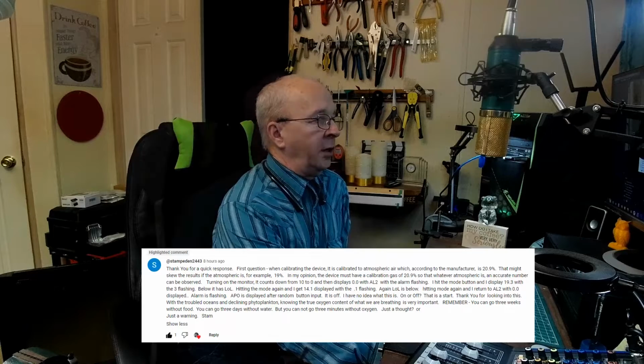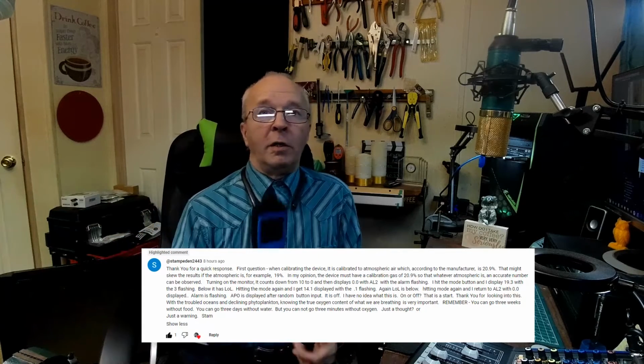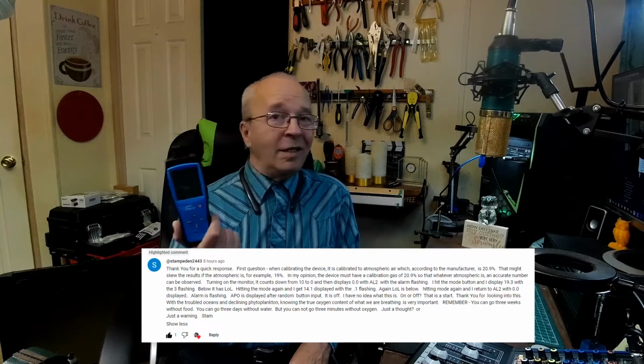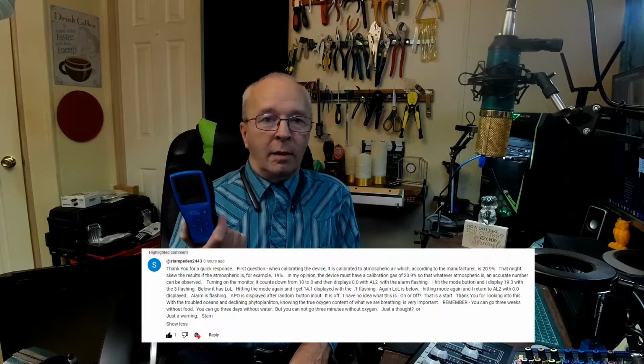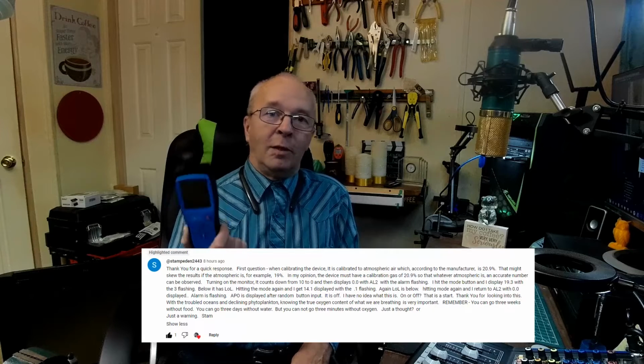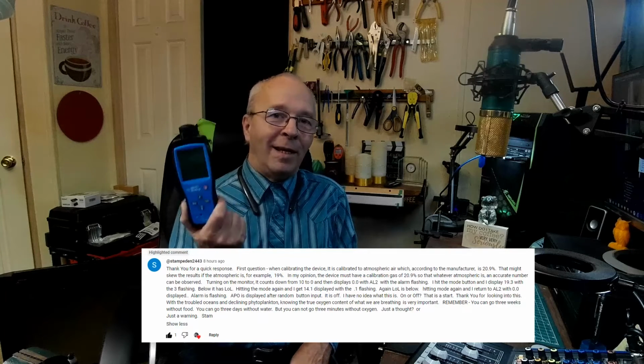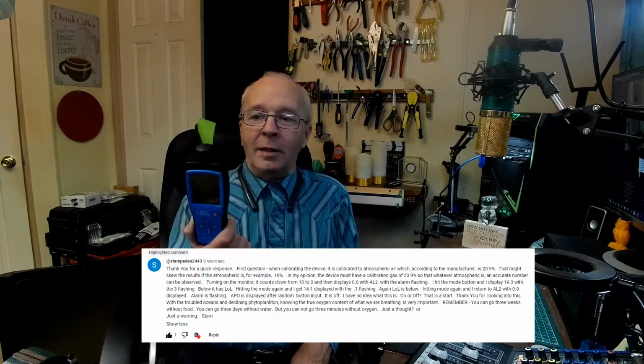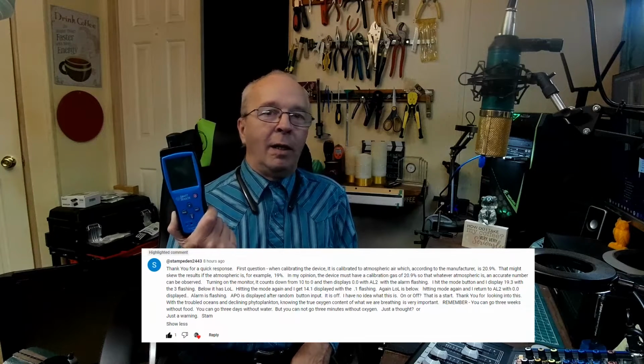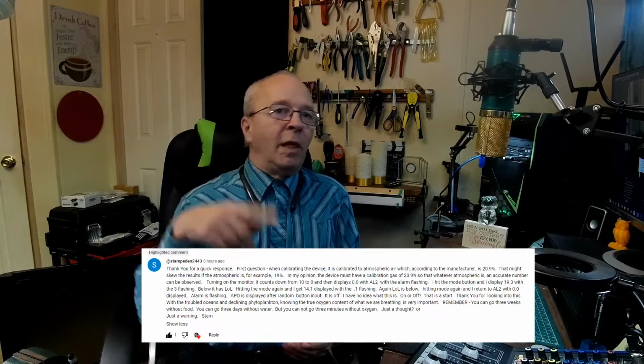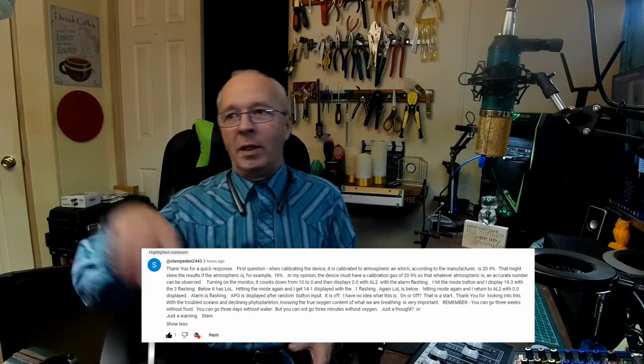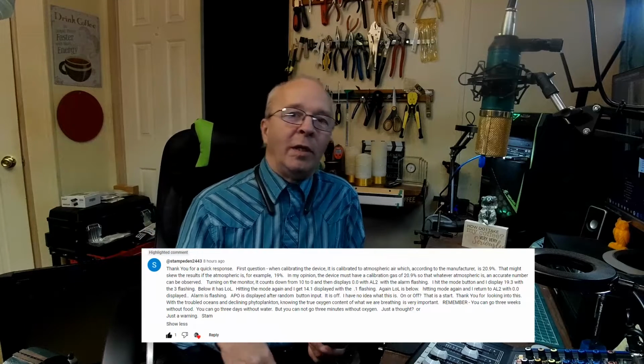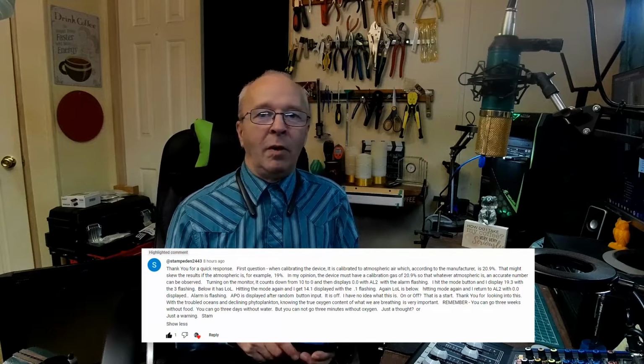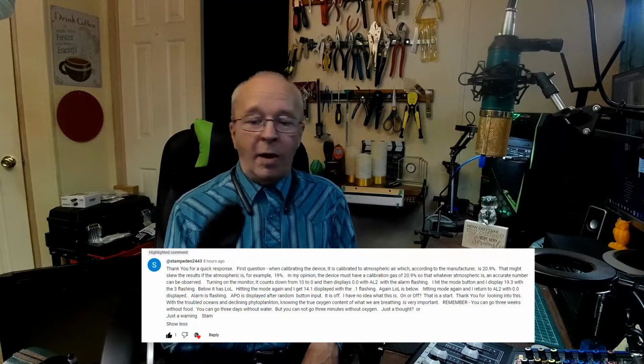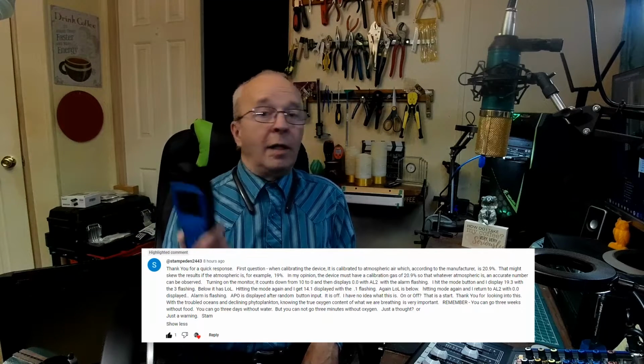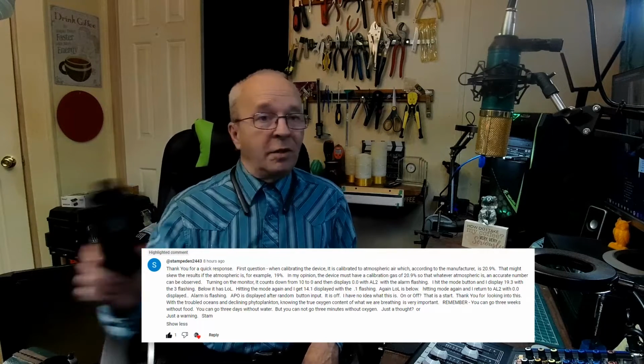I also have the smart sensor AR8100. I really haven't used it, and as a matter of fact, I forgot I even had it until you sent me this question. Then I was like, oh man, I need to get that thing out and start playing with it. So I actually was trying to mess around with this to calibrate it, and I think I messed it up. It started flashing different numbers up and down. It would go to 0, and then it would go up to 30%, then it would go back down to 20.9, then it would drop to 15, then it would go all the way down to 0, and then back up to 30. So it was going nutty.